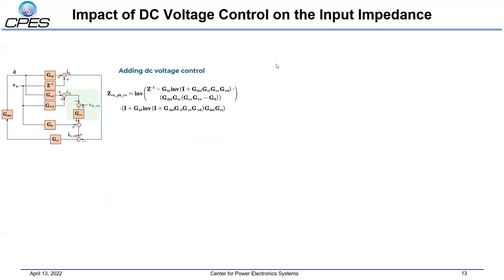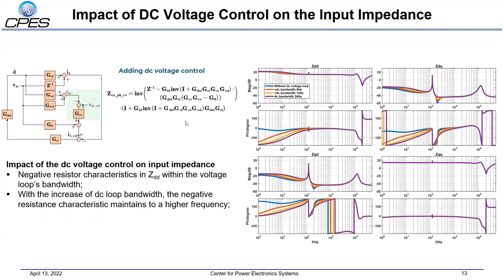After including the DC voltage control, the block shaded in green is added to the small-signal model, where GCI represents the dynamics of the DC voltage controller. The input impedance can then be calculated using this equation. This figure shows the impedance results for four scenarios: without DC voltage controller, and with different DC voltage control bandwidths of 6 Hz, 15 Hz, and 24 Hz. Adding the DC voltage control mainly impacts ZDD at low frequency, and also ZDQ and ZQD because of the coupling effect. This is because the D axis is aligned with the original circuit input voltage vector, and due to unit power factor control, the AC side power is delivered through the D channel to the DC channel. Having DC voltage control also results in a negative resistor characteristic of the ZDD element at low frequency. With increasing DC loop bandwidth, the negative resistance characteristic extends to a higher frequency.